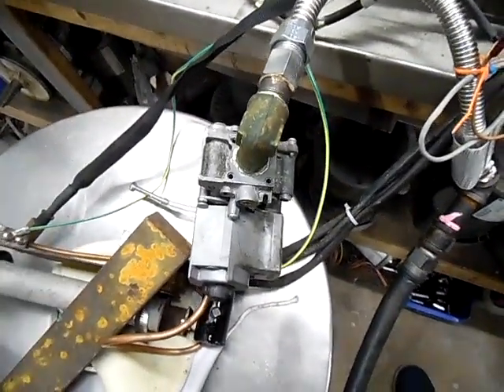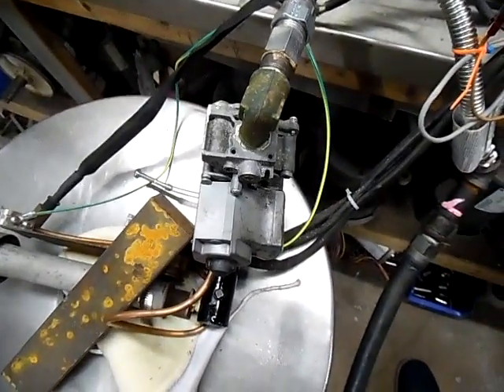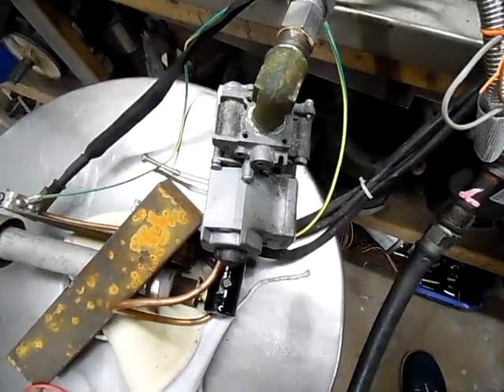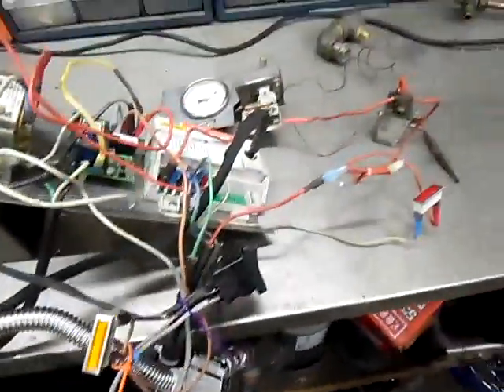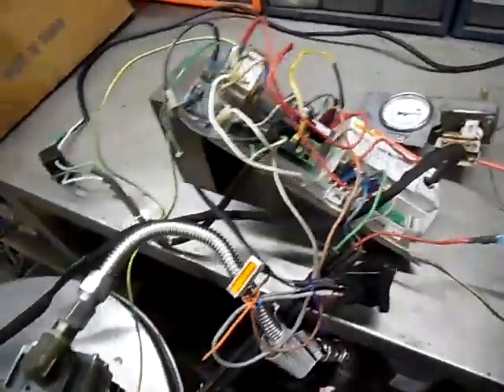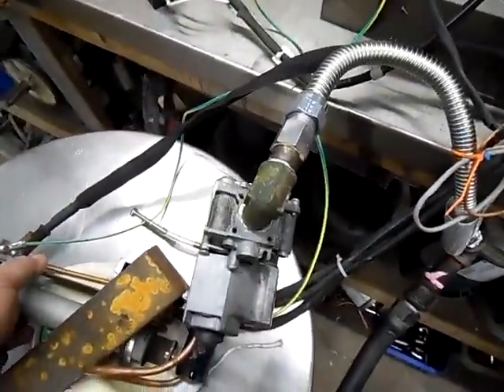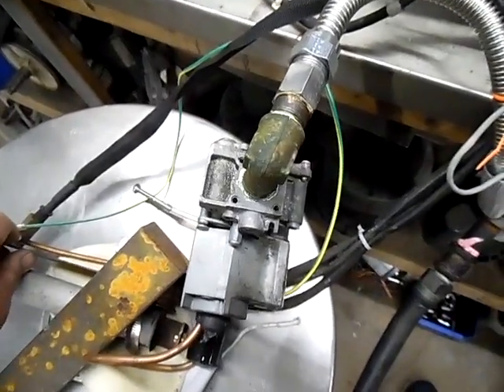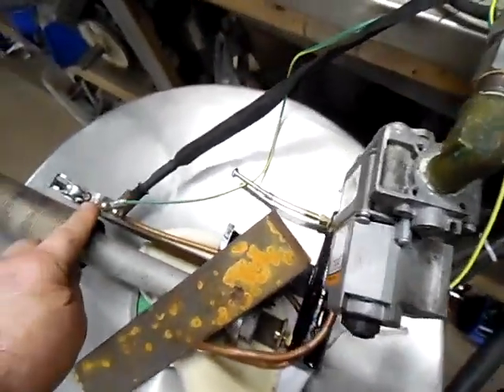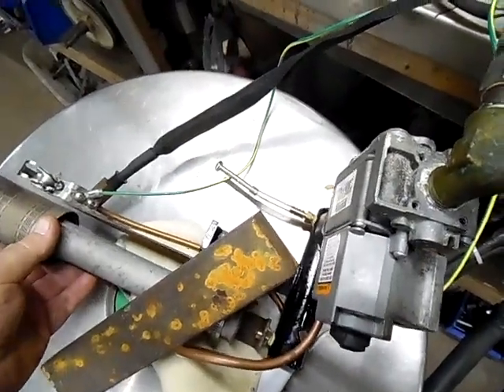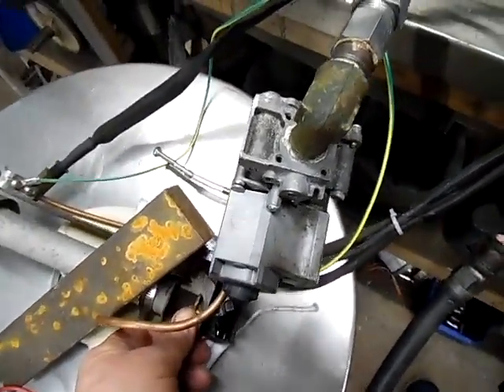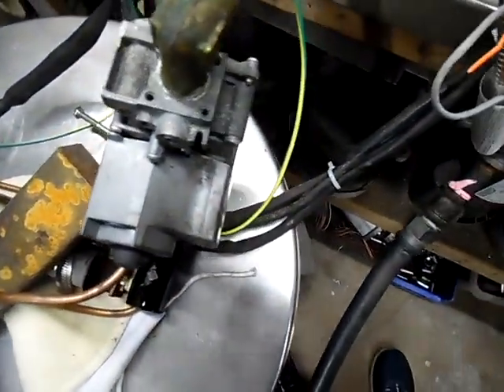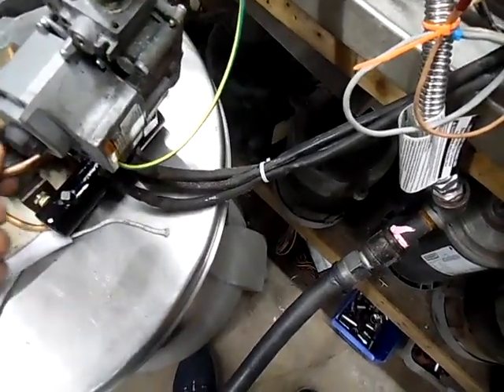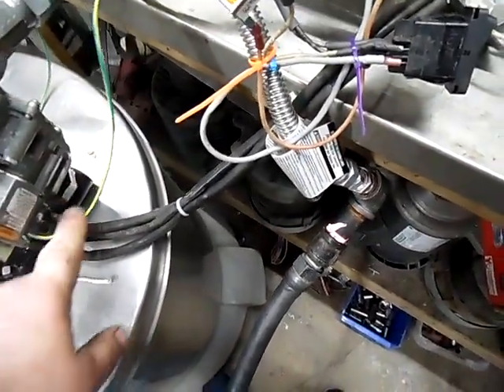What happens is this acts as a flame rod coming back to your box. The voltage is converted, and it reads DC voltage off the rod back to the box, and it's looking for a minimum. What we've started doing on these, because if you notice on the Vulcan and the same style kettle, there's a long bar that mounts the pilot, and these burners do not mount solid in the machine. They kind of float around on the jet and the bracket in the back. And what happens is you don't get a super ground. Your only ground really is through your pilot tube, and then your valve has a ground.